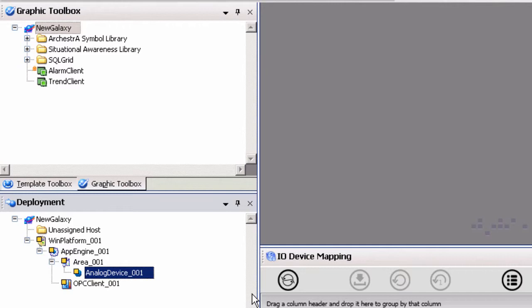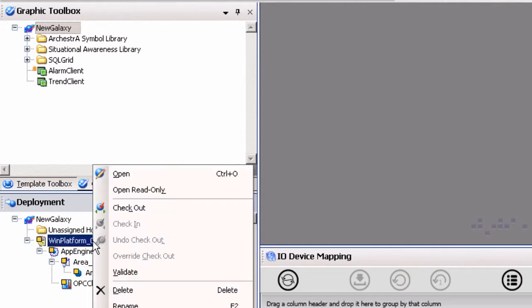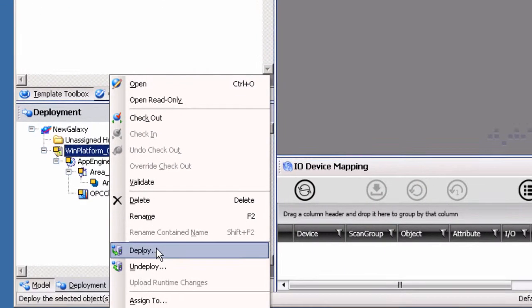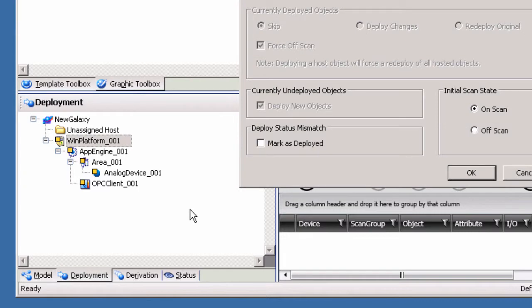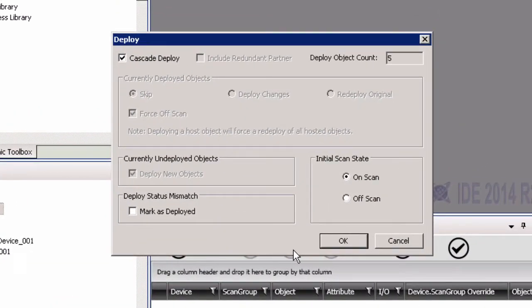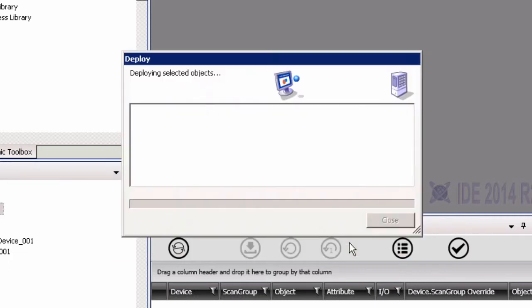The Analog Device object can now be assigned to the Area System object in the deployment view. To do so, drag and drop the object from the Unassigned Host folder under the Area object. Now that all objects have been created and assigned, the next step is to deploy the Galaxy. Right-click on the WinPlatform object in the deployment view and select Deploy. Leaving the default settings selected will deploy all objects configured. Click OK to begin the deployment process.